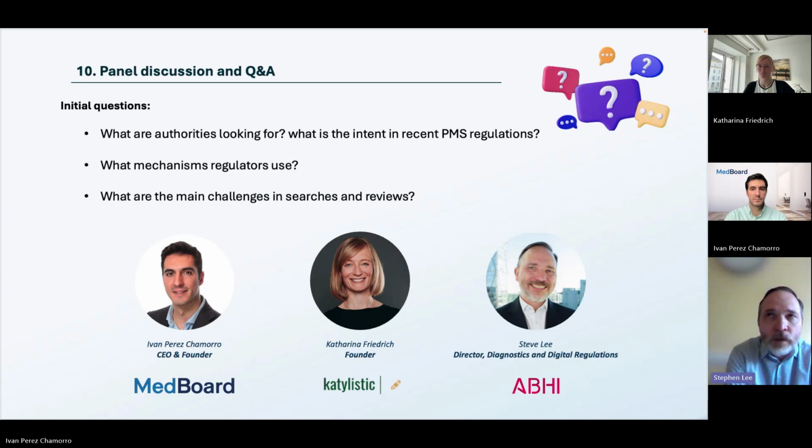For some incidents, there's going to be a full-blown investigation, and the regulator is going to be looking at not just the report from yourself or from the user. They're going to be looking at a whole load of other databases, expert opinions, clinicians, and they're going to find a whole lot. They'll also be going to the conformity assessment body, saying, how has this manufacturer been working with you in terms of their vigilance reporting procedures and their post-market surveillance procedures? Are they generally compliant, or are there any concerns about these products? That could be huge, loads and loads of questions that you weren't prepared for.